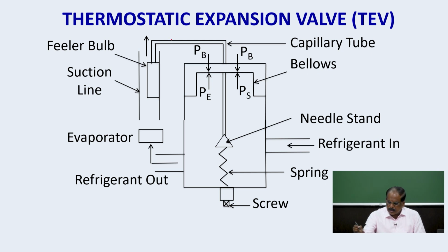It is attached with the help of a capillary or a narrow tube. This tube is also filled with a liquid that is called power fluid. It can be a different liquid or it could be the same refrigerant which is employed in the system.